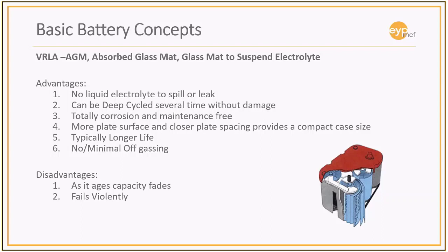When we say that it's a 10-year battery, we typically mean that it's a 10-year warranty life, but you typically have to change these in 5 to 7 years, whereas in a 5-year battery, you typically have to change them in 3 to 5 years. That flooded cell battery is a 20-year battery, and you typically need to change those in 14 to 16 years. The reason they call them 10, 20, 15-year batteries is that there's a warranty on it, and that warranty is typically a degrading warranty. So in year 1, you get a full replacement, but in year 10, depending on the type of battery, you get some prorated value associated with those batteries.